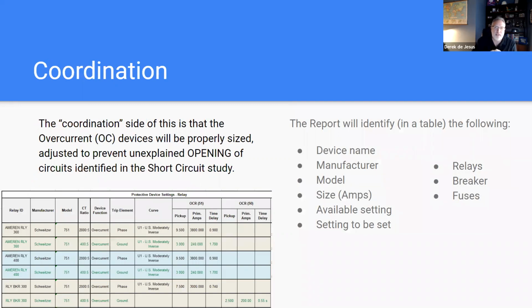So using the short circuit side, you're going to have all of your devices modeled, your breakers, your relays, your fuses. And then typically right around chapter 4 of the power system study, you're going to have the coordination table. The coordination table is going to look very similar to what you have on your screen, where you're going to have your devices called out on the left, followed by the manufacturer, the model of that device, the current rating, as well as any other available settings that need to be provided.